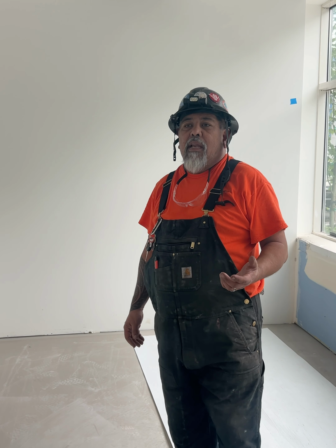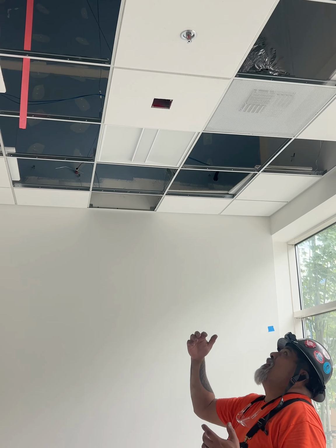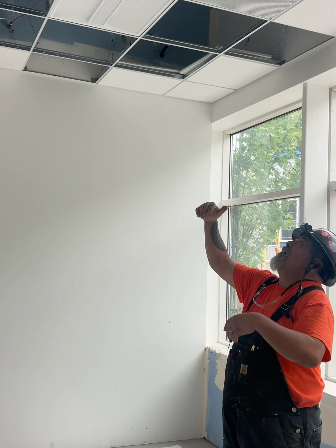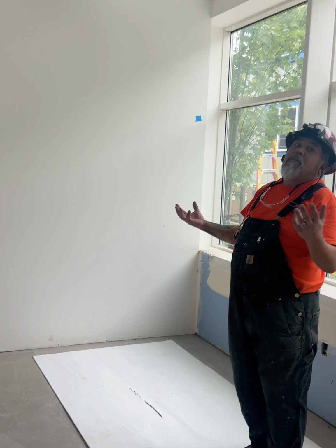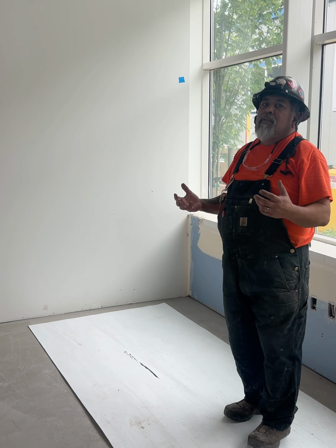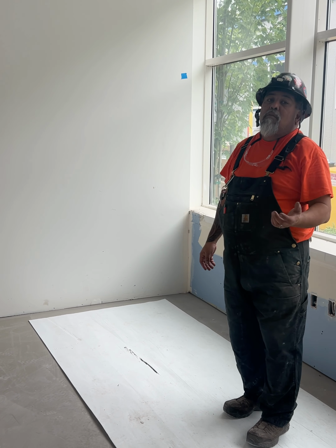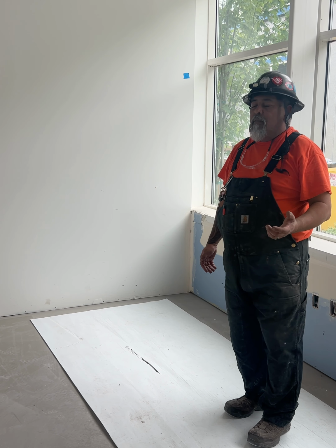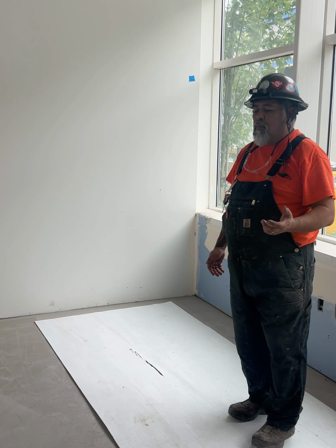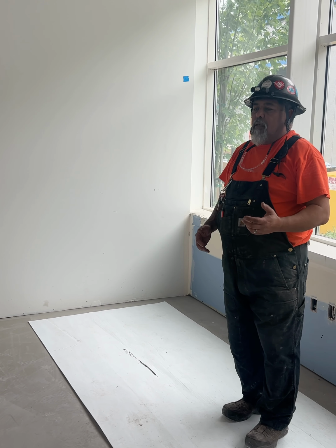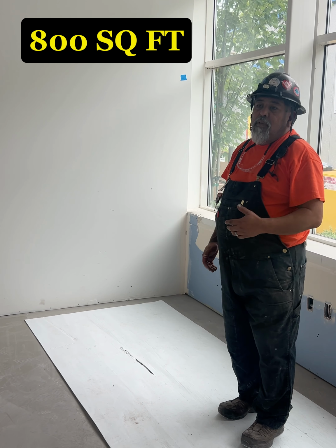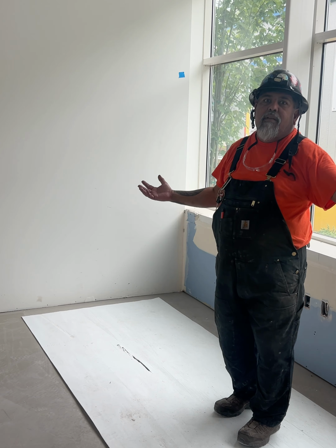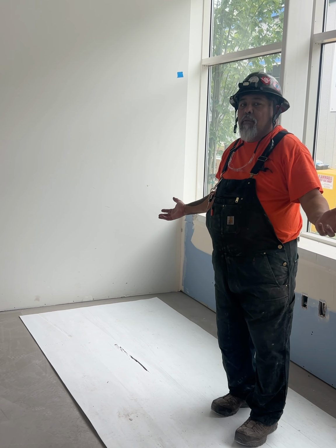What could happen is that the learner might put his box right there and the lights are right here, and you've got ductwork right there, and it throws everything off on your spacing of the walls. So the small room rule was applied for a situation like that. Keep in mind that the small room rule is for up to 800 square feet, which could probably have 4 sprinklers in that big of a room. If it's 700 square feet, you could still apply it.